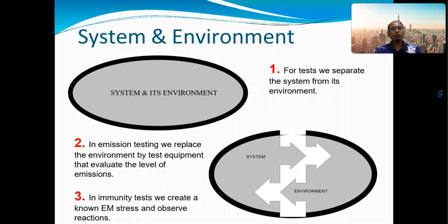All right. Now we look at the system environment. The first step, we separate the system from its environment. So we have to separate the medical device from the environment. The second is emission testing, where we replace the environment with test equipment that evaluates the level of emission.